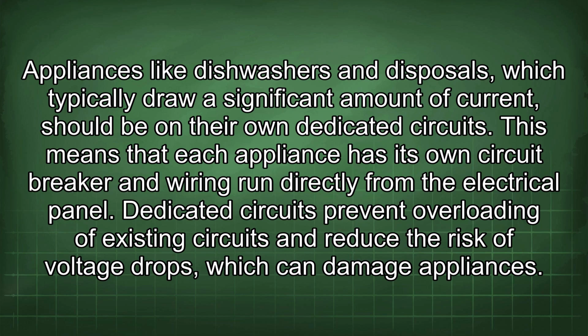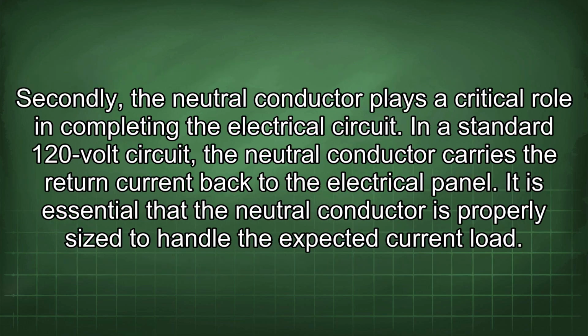This means that each appliance has its own circuit breaker and wiring run directly from the electrical panel. Dedicated circuits prevent overloading of existing circuits and reduce the risk of voltage drops, which can damage appliances. Secondly, the neutral conductor plays a critical role in completing the electrical circuit. In a standard 120-volt circuit, the neutral conductor carries the return current back to the electrical panel. It is essential that the neutral conductor is properly sized to handle the expected current load.